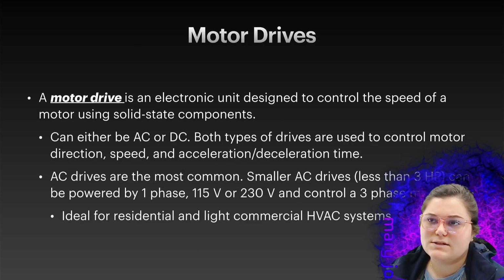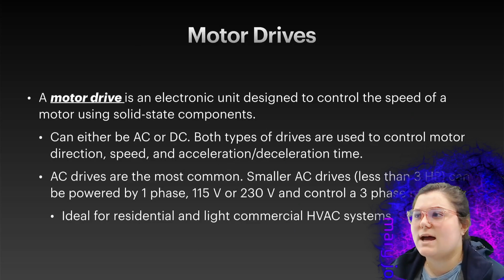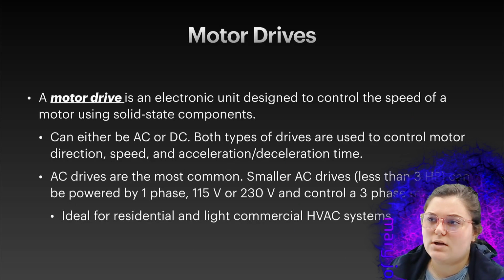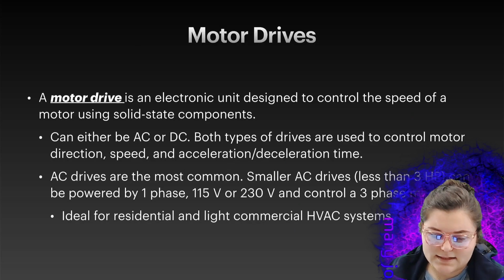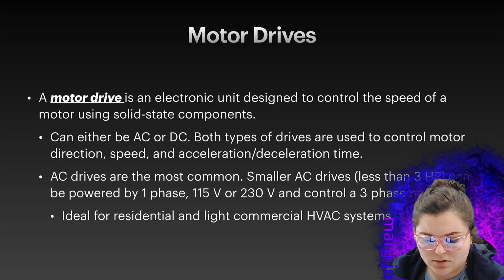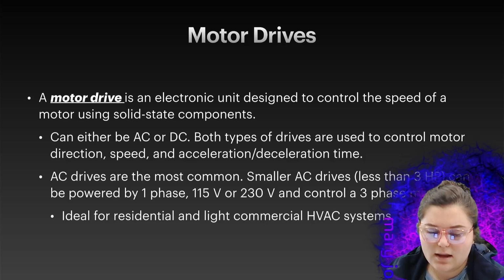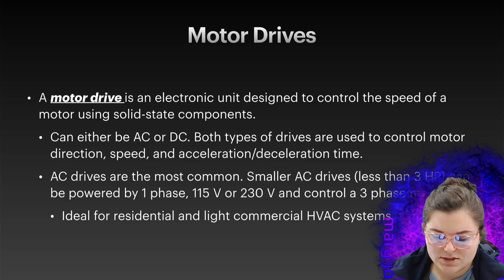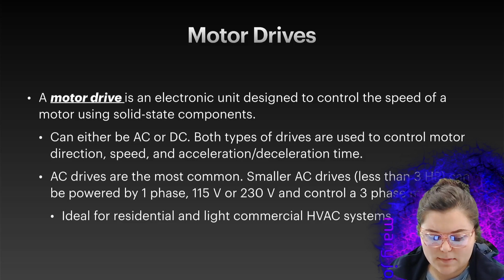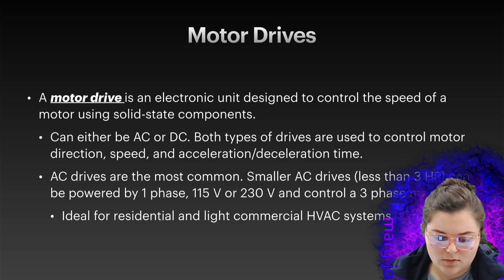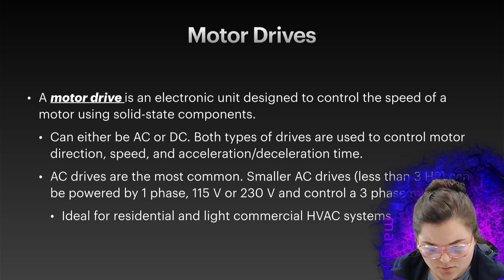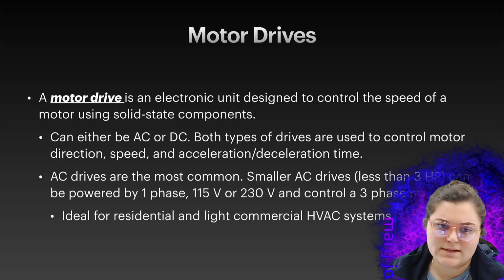Motor drives. A motor drive is an electronic unit designed to control the speed of a motor using solid-state components. They can be either AC or DC. Both types of drives are used to control motor direction, speed, and acceleration or deceleration time. AC drives are the most common. Smaller AC drives, that's going to be less than 3 horsepower, can be powered by one phase, 115 volts or 230 volts, and they can control a 3-phase motor. They're ideal for residential and light commercial HVAC systems.